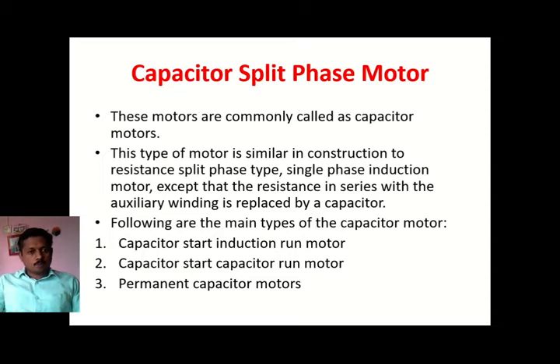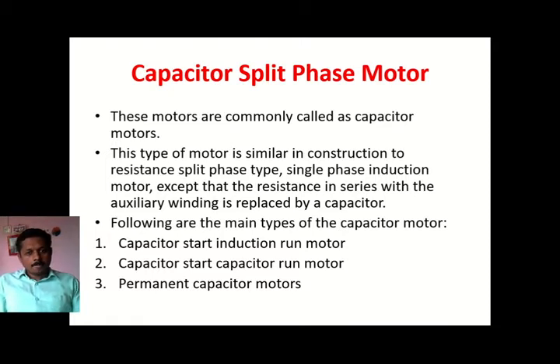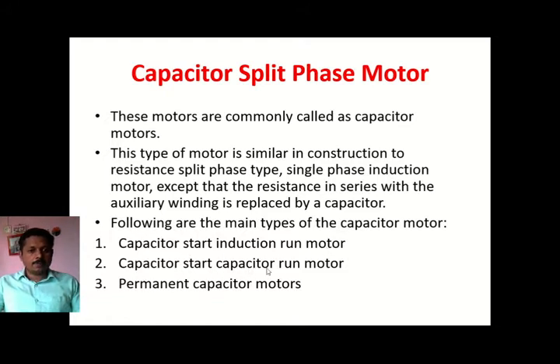Capacitor split phase motor. The most commonly used motor nowadays is the capacitor motor. This type of motor is similar in construction to a resistance split phase motor, except that it has a capacitor rather than a resistor in series with the auxiliary winding. As per the application or use of capacitors, we have three types of capacitor motors: first is capacitor start induction run motor, second is capacitor start capacitor run motor, and third is permanent capacitor motor.